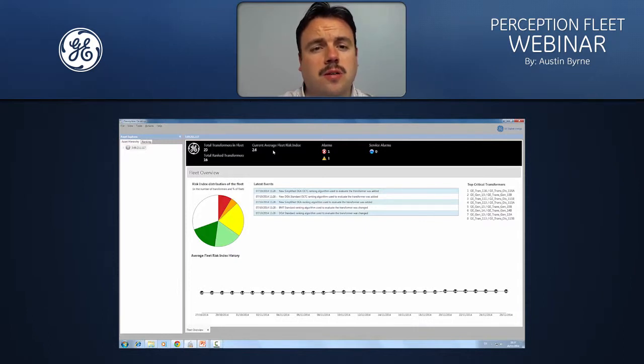You can see in the body of the dashboard we have our risk index distribution of the fleet represented in a pie chart, and that shows you the distribution of the different risk indexes within the entire fleet and how much of your fleet is in a particular risk category. So you can see for the risk index of 5, we have 2 assets, and that represents 9% of the fleet. For risk index of 4, we have 1, and that represents 4%. And you can see how it breaks down for the rest of the risk indexes here. This white section indicates any assets which are not being evaluated. So that's currently 7 assets, and that's 30% of the fleet.